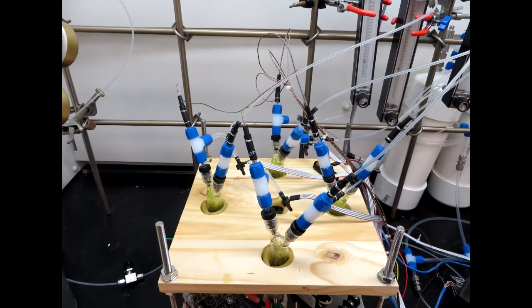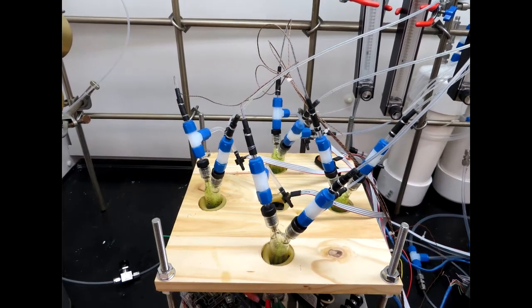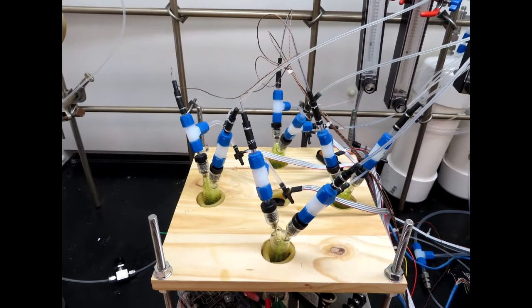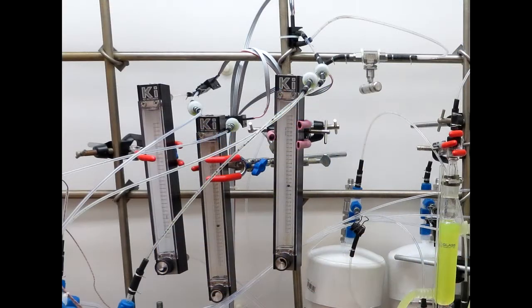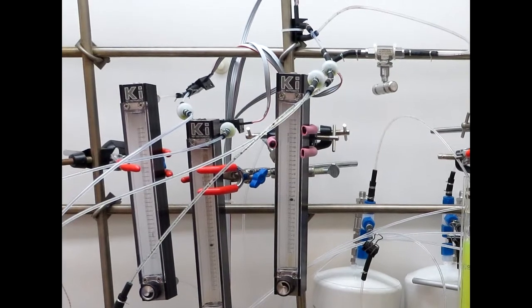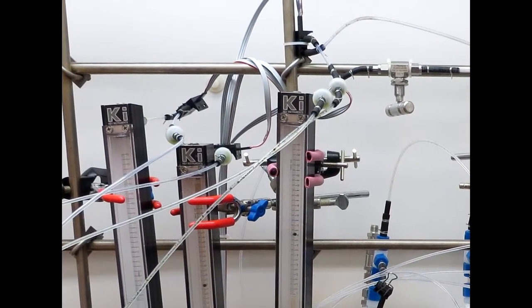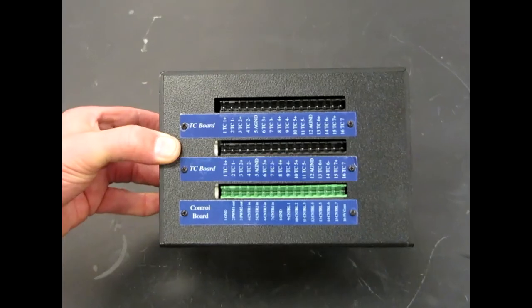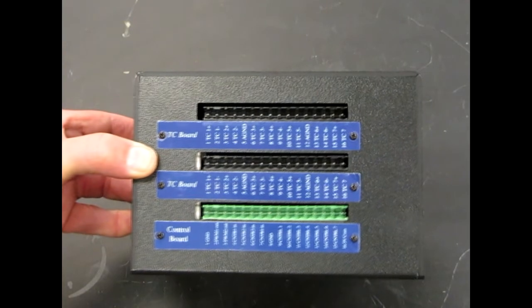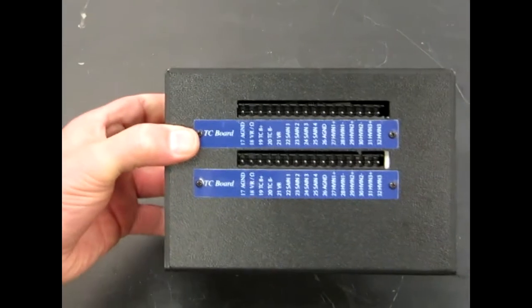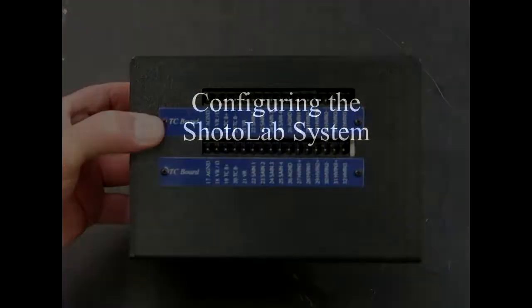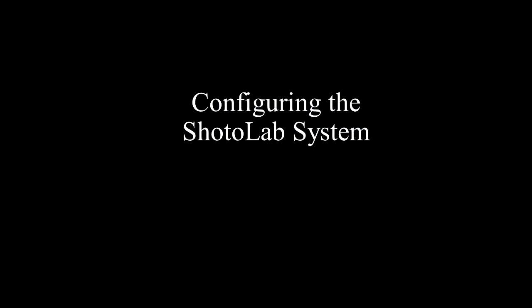Here's a top view of the reactor showing the pressure transducer, the thermocouples, the gas inlets and outlets, and how everything was connected. Here you can see the flow controllers with the flow transducers mounted on the back. Since we only had 3 flow tubes, I'm using a valve and electronic flow meter for one reactor. You can see I'm using 2 TC boards instead of the typical TC and SP board that are normally sold with the system. Once everything was connected, here's how easy it is to configure the Shoto Lab software.